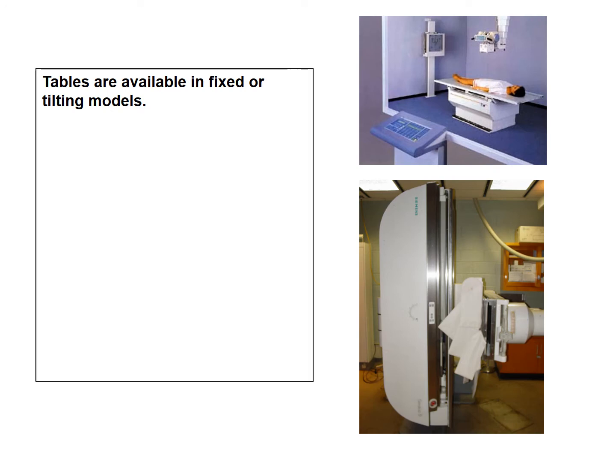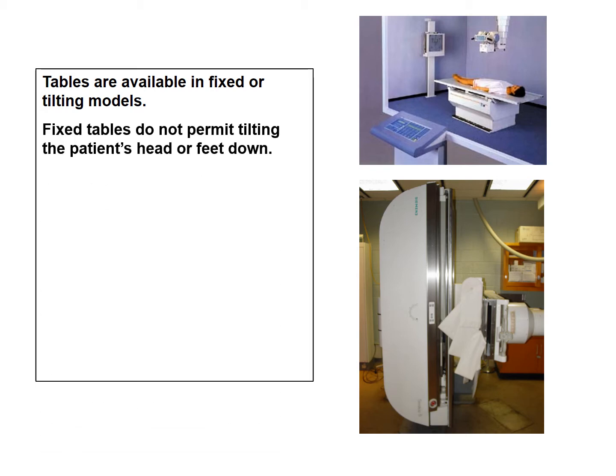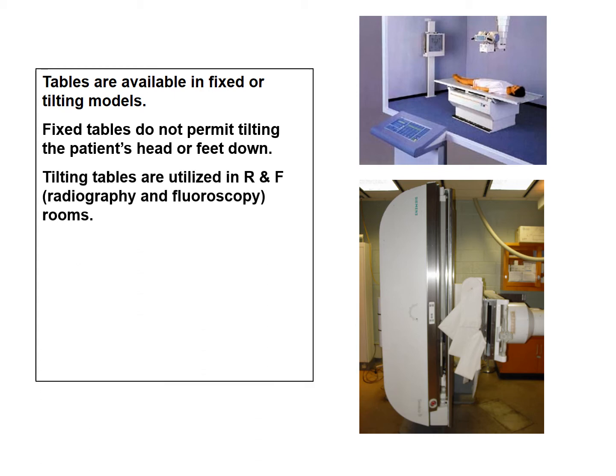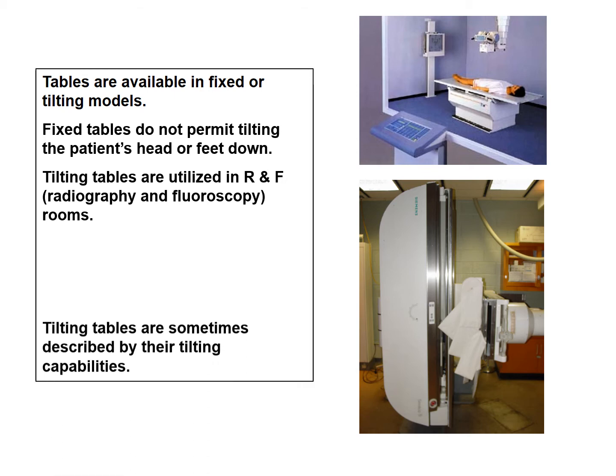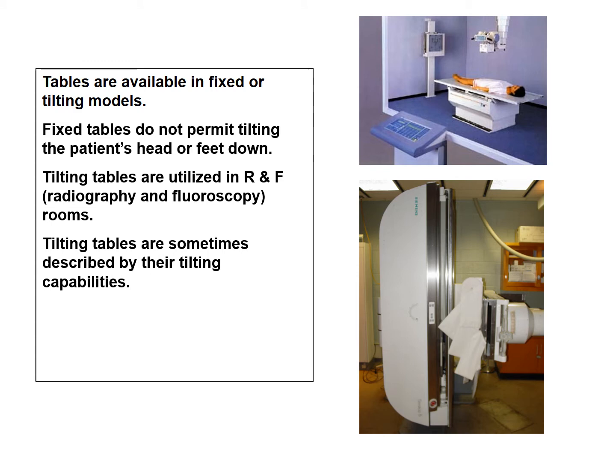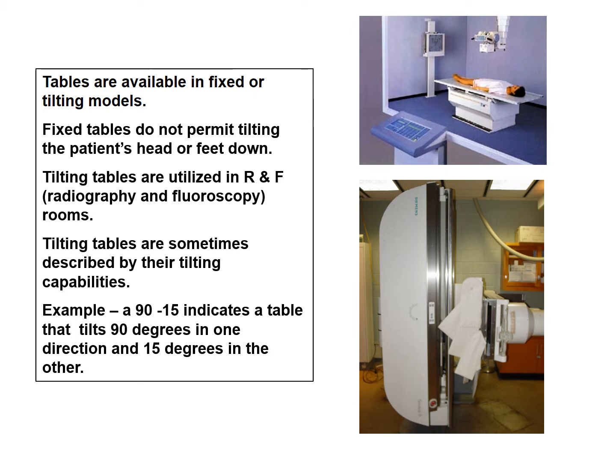Tables are available in fixed or tilting models. Fixed tables do not permit tilting the patient's head or feet down. Tilting tables are used in R&F rooms, radiography and fluoroscopy rooms. Tilting tables are sometimes described by their tilting capabilities. So for example, a 90-15 indicates a table that tilts 90 degrees in one direction and then 15 degrees in the other. 15 degrees would be the Trendelenburg position.